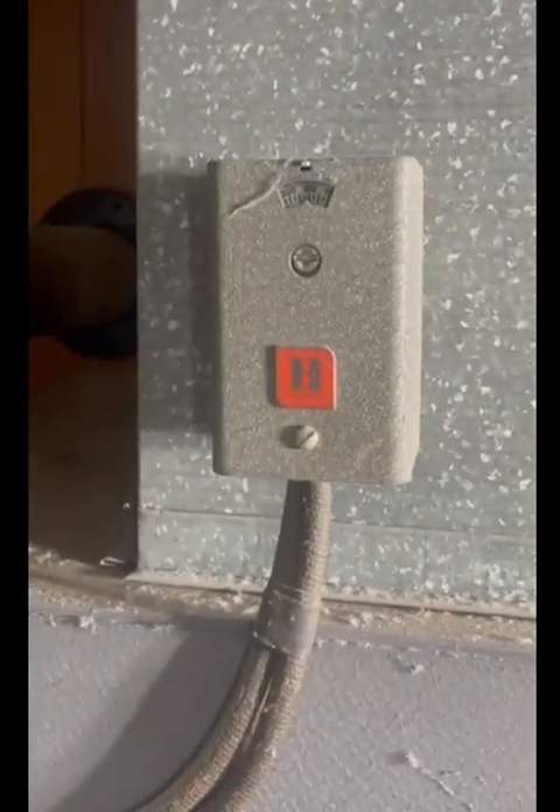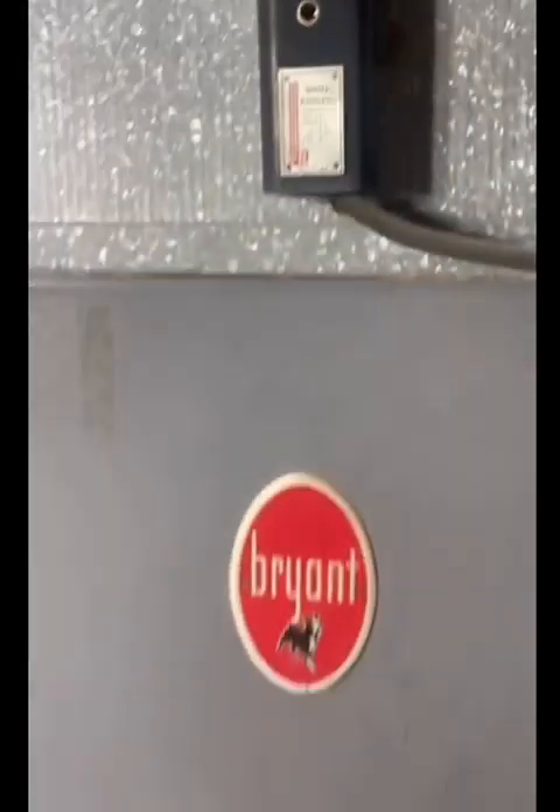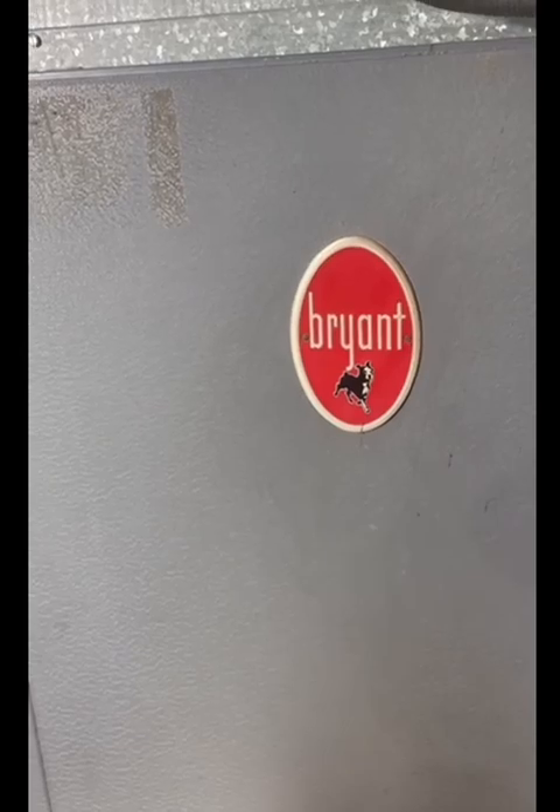You've got a second high limit, and this setup they put in — why would you have a second high limit? But that's a Honeywell, and this is a White-Rodgers. They're probably both original. This one probably turns the fan on and off, and this one is the high limit. Sorry for the confusion everybody, but it's part of the real world.